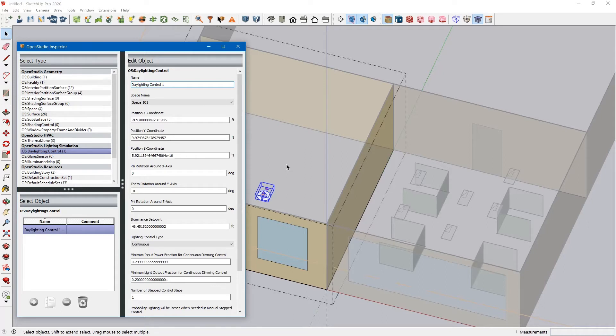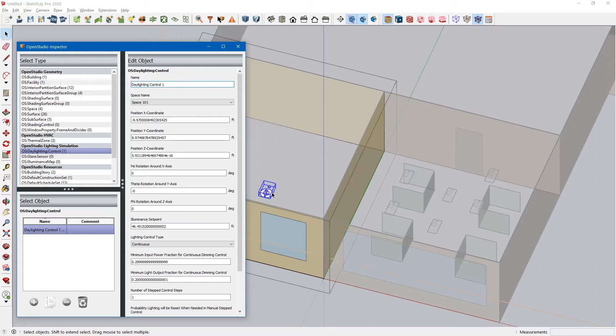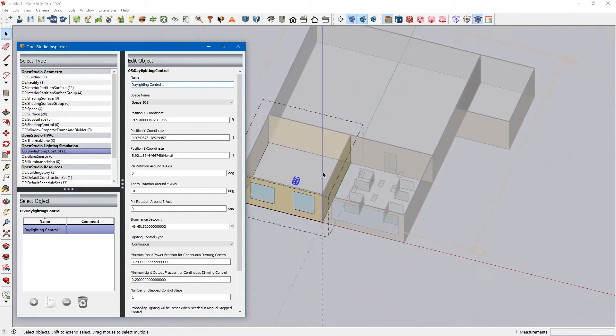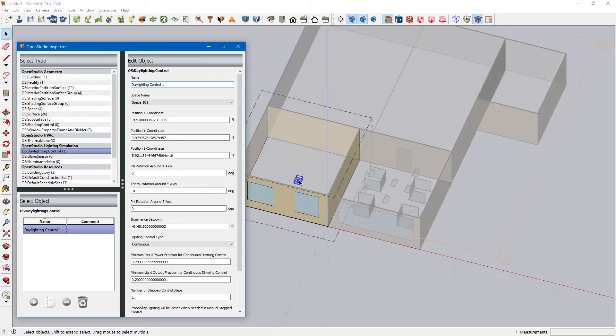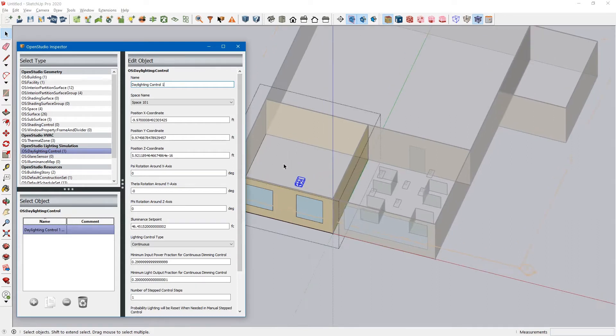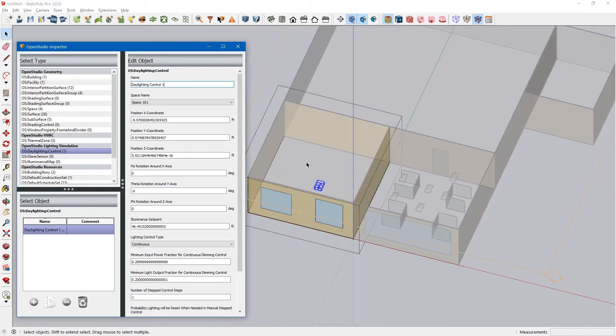It's important to note that you can drop these into individual spaces. But Energy Plus will only allow up to two daylighting controls in a thermal zone. If these two spaces were part of a thermal zone, this daylighting control would actually control this space and this space, because they're part of one thermal zone. To get around that, it might be best to assign separate thermal zones to each of these spaces, if needed.